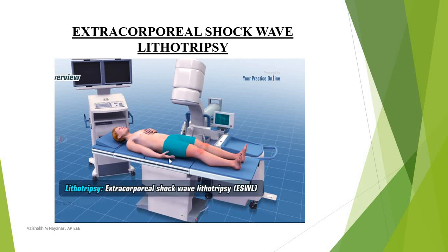The water-filled coupling device is placed at the level of the kidney. A biplane X-ray system is built to monitor and identify the position of the kidney stone. A high voltage pulse is applied to a spark gap and the discharge produces a shock wave that is propagated through the water.